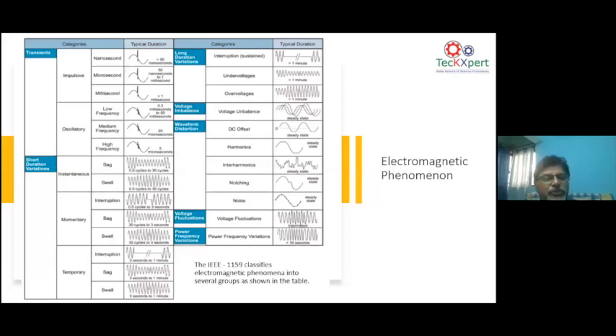Similarly, when it comes to short duration voltage variations, you have sag or swell or some interruptions. These things again remain only for short durations of cycles. So transients and short duration variations we only describe in terms of cycles. We don't talk in terms of seconds or minutes. For example, a sag is a drop in voltage. As we all know, plus or minus 10% is the voltage we try to maintain. So if the voltage drops below 10%, let's say to 70% or 80%, for a period of a few cycles, then we say it's a sag.